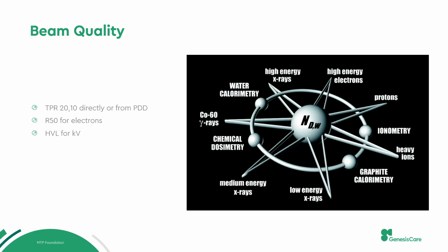And what's the advantage of using PDD? Straightforward. The setup is very simple. Yeah, very simple. But for TPR, is electron contamination an issue there also? No. Why? Because you are taking two measurements at depth, right? At 10 cm depth, there is no contamination.